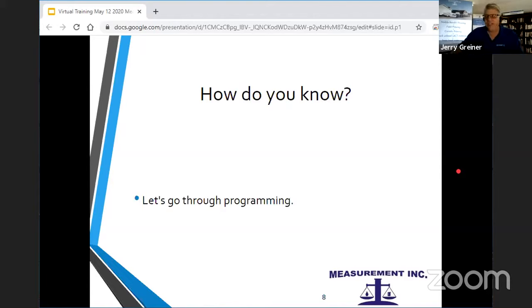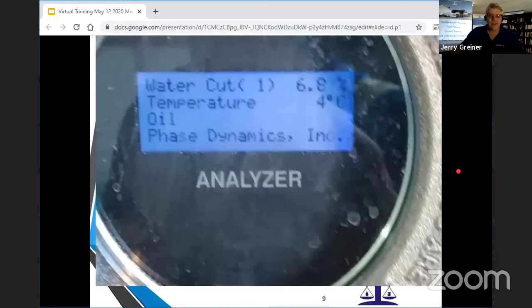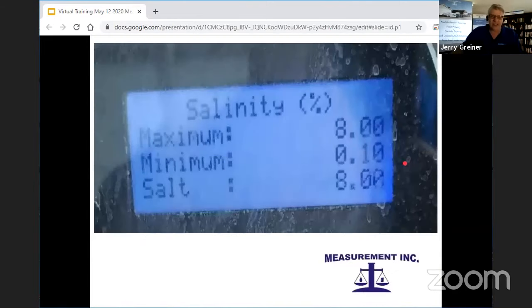So how can you tell the calculation is overrange? Well, in the programming of these, if you can see on that, it'll show water cut. There are different screens. It'll go water cut, temperature, and the oil. And the next screen, there it is, salinity. You get to one of these screens, it shows what the salinity is, and it'll show the salinity range on these, which is 8% is the high end, the minimum is 0.1, and it's set at 8.00.